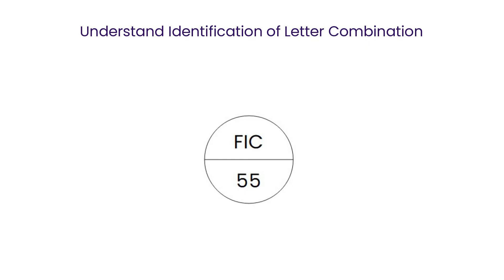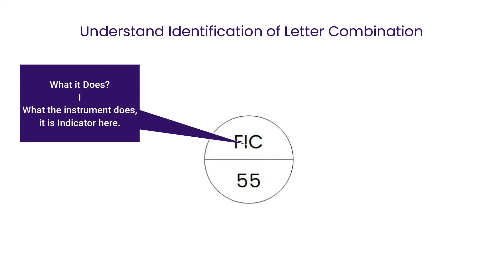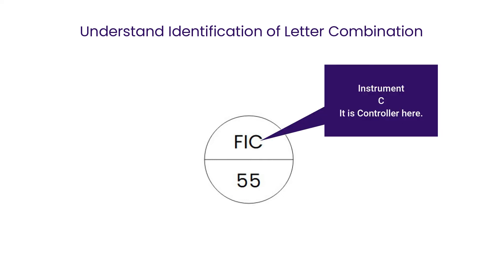Now let's understand the identification of letter combinations. In this symbol, the first letter is the variable being measured — in this case, F means flow. The second letter denotes what it does — in this case, I means indicator. The third letter indicates the purpose of the instrument — in this case, C means controller. And 55 is the number used to identify the loop number.